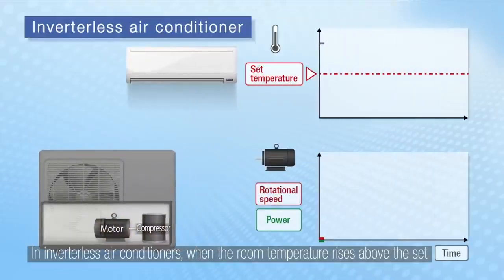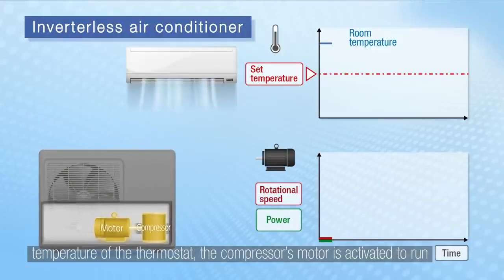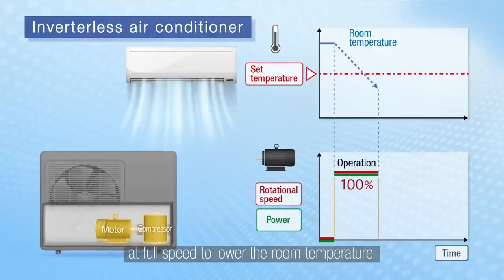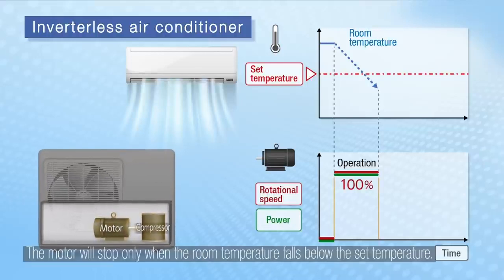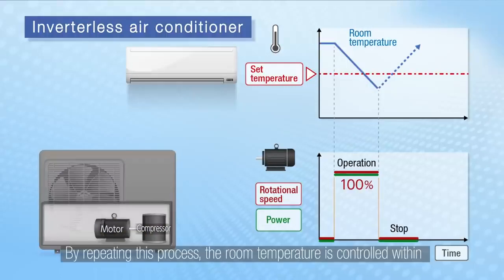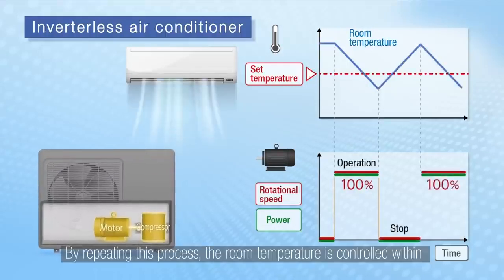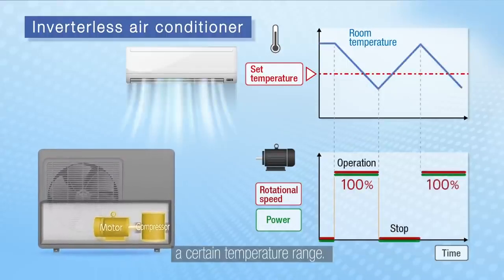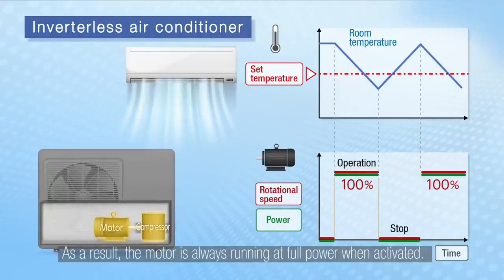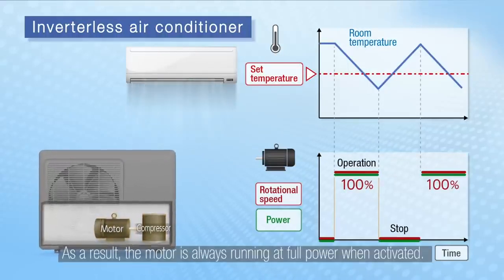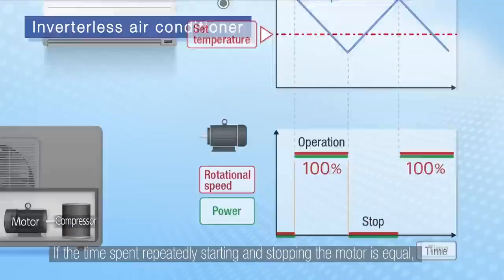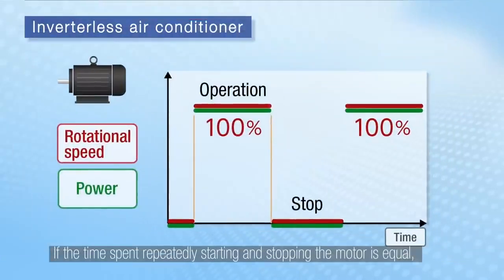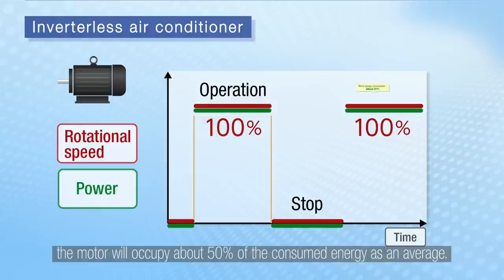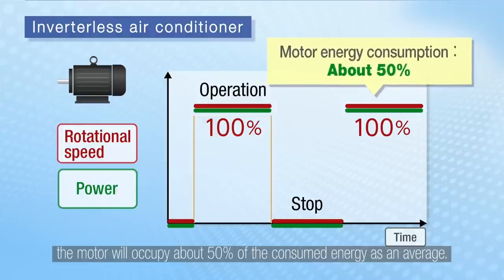In inverterless air conditioners, when the room temperature rises above the set temperature of the thermostat, the compressor's motor is activated to run at full speed to lower the room temperature. The motor will stop only when the room temperature falls below the set temperature. By repeating this process, the room temperature is controlled within a certain temperature range. As a result, the motor is always running at full power when activated. If the time spent repeatedly starting and stopping the motor is equal, the motor will occupy about 50% of the consumed energy as an average.